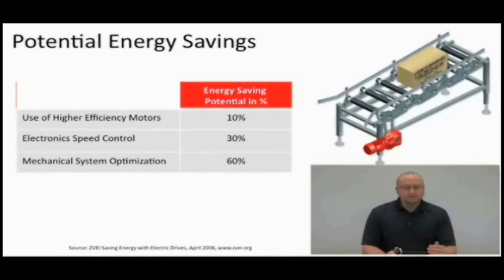If we look at the three main things that people think of, high efficiency motors or premium efficiency motors, that's been a big concern with the EPAct law and also with the new EISA law. I'll explain those a little bit more later on in the presentation. But there's some other things we can do. By introducing a VFD into the system, we can control the speed of the motor, vary the speed, rather than running it directly off the mains. And we also have mechanical components. We have a potential to save some energy with all three of these components, but by far the largest impact that we can make is with the mechanical components. And remember I said there's a potential energy savings in percentage, they're relative.